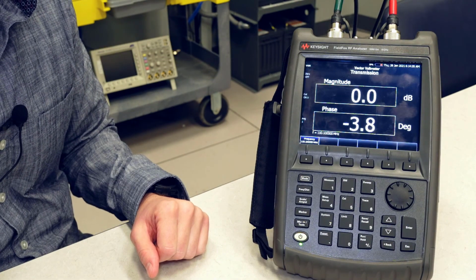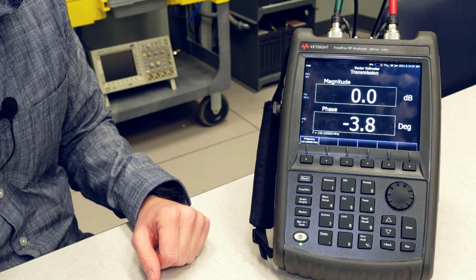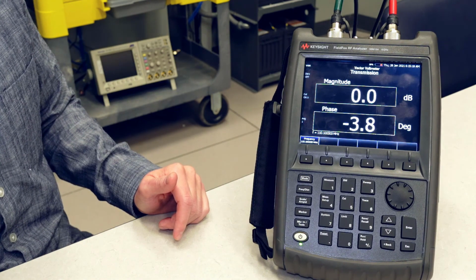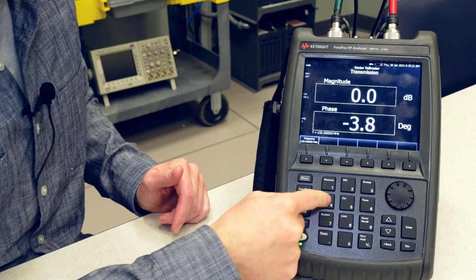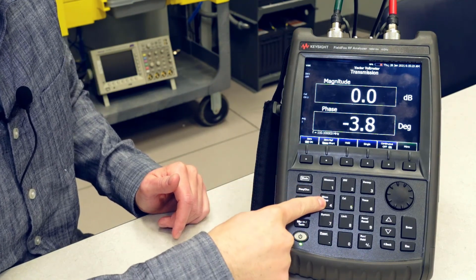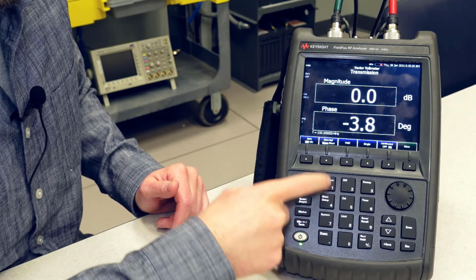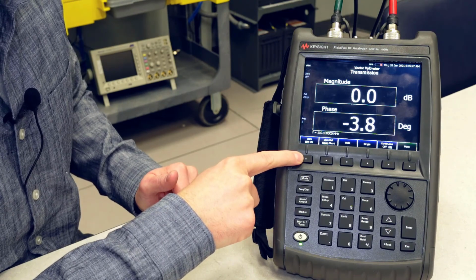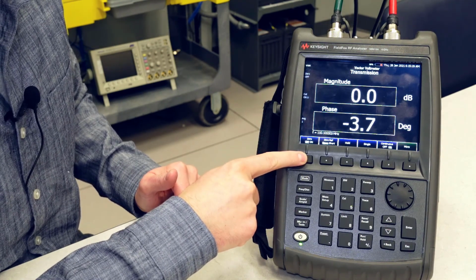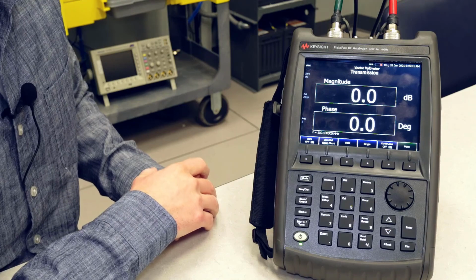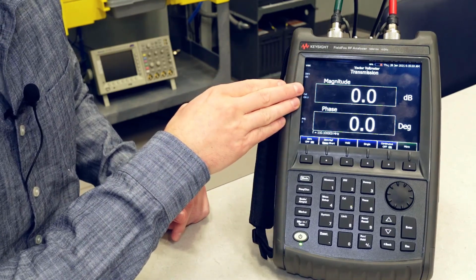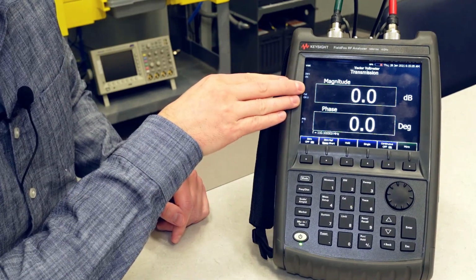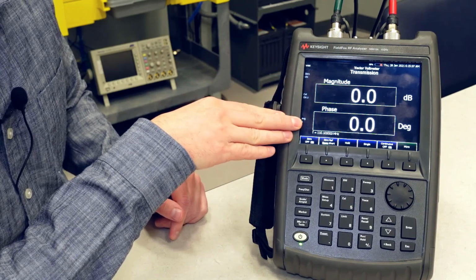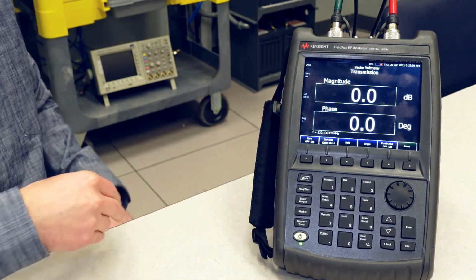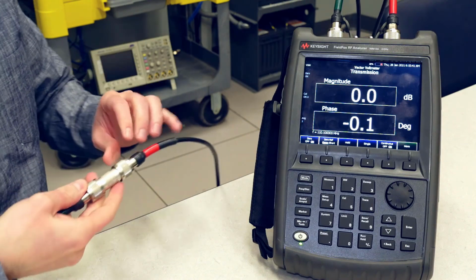Okay, I just completed a full 2-port mechanical calibration, and the next step is going to be to normalize or take a 0 reference. And so if we hit measure setup, the number 4 key, we can see that the 0 is currently turned off. And so all we need to do is simply turn it on. And now I have still 0 dB. If there was anything there, that would have zeroed it out, just like you see here. And then, of course, the degrees is now zeroed. And now we can connect our device under test.